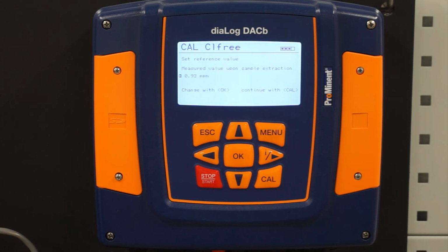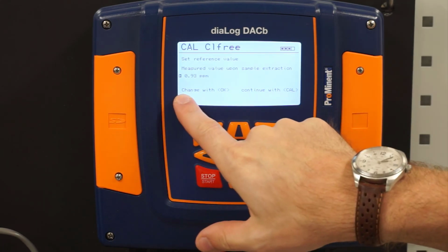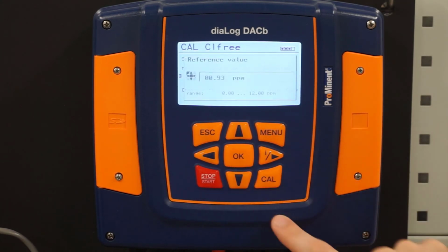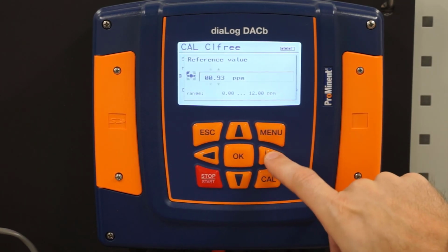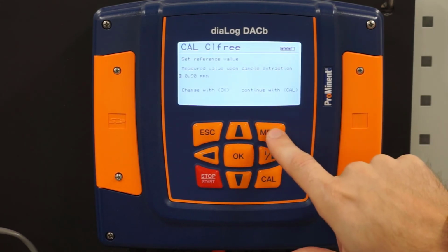In that case, that's pretty close. I don't know if that's necessary to calibrate at that point. There's going to be some error in the DPD test. So I don't know if I personally would recommend changing at that point for a calibration. But if you wanted to, you can see if I hit OK, it's going to allow me to change that. And I can dial it down to 0.9, hit OK, and then continue with cal.